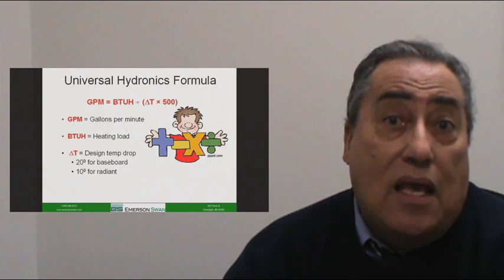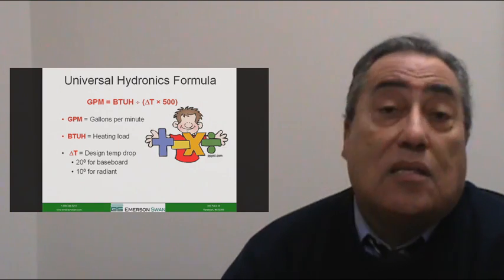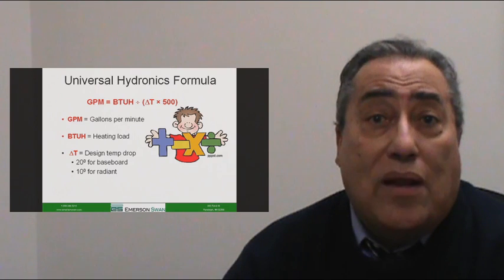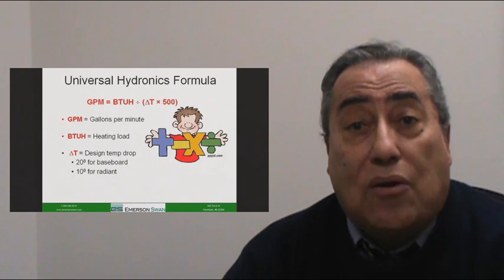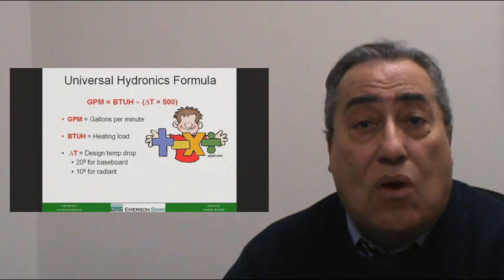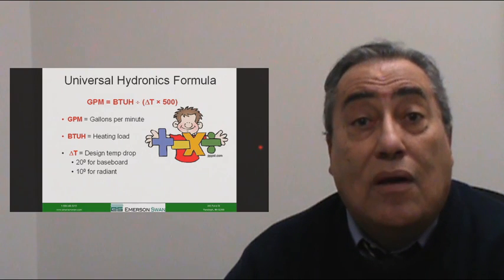On a radiant system, the Delta T is 10 degrees. In a typical radiant system, it might go out at 130 degrees and come back at 120 degrees. If the Delta T is any wider than that, you might end up with cold spots at the end of the run. So we design radiant systems around a shorter Delta T.